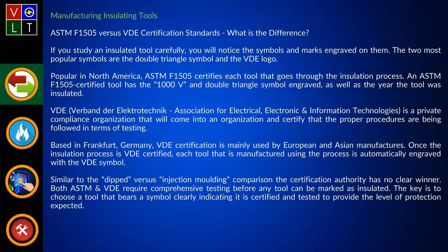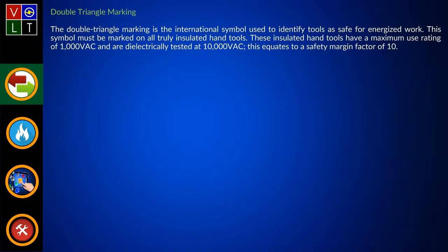So that's some information on that. I wanted to point out that this double triangle marking, when they perform this testing and engrave it on these tools, clarifies that the insulated hand tools have a maximum use rating up to 1,000 volts, but they're dielectrically tested at 10,000 volts. So that equates to a safety margin factor of 10.